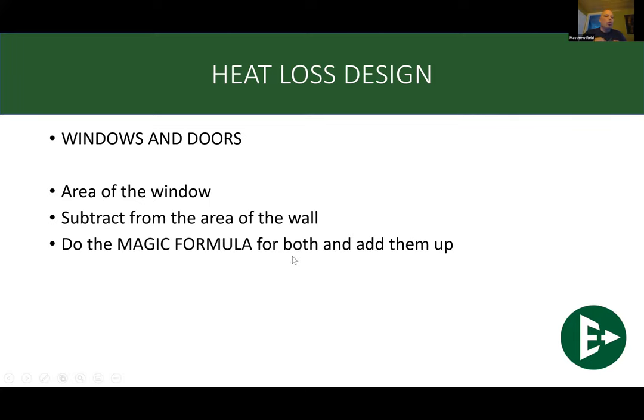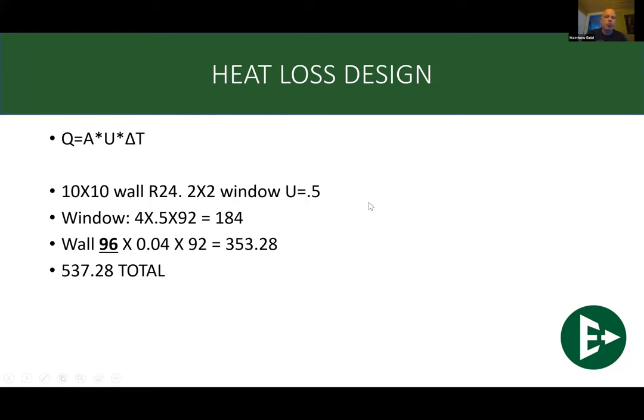Now, what about windows and doors in that wall? What we do, again, is fairly straightforward. We take the area of the window, subtract it from the area of the wall, do the magic formula for both of them, and then we just quickly add them up. So it's really straightforward and easy. We take that 10 by 10 wall, and I've changed the R value a little bit, with an R24. It's got a 2 by 2 window and it's got a U value of 0.5. So we find the BTUs required for the window, which is 2 times 2, times 0.5, times 92, which is your temperature differential. So you get 184. That's your BTU required for the window.